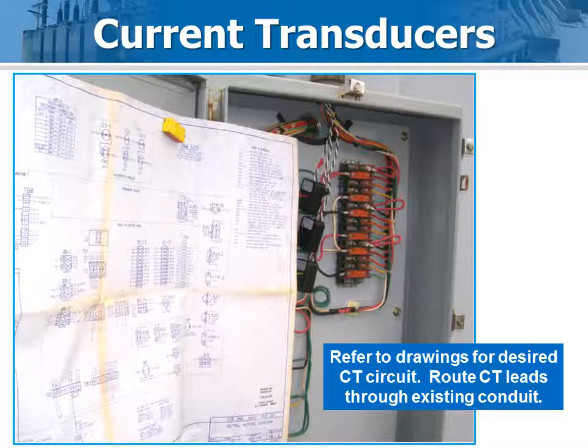Identify the bushing CT circuits and place the current pickup coils around those conductors. This CT ratio, referred to 1, is programmed into the optimizer when you set it up. Refer to the wiring diagrams for exact ratios and identifiers.